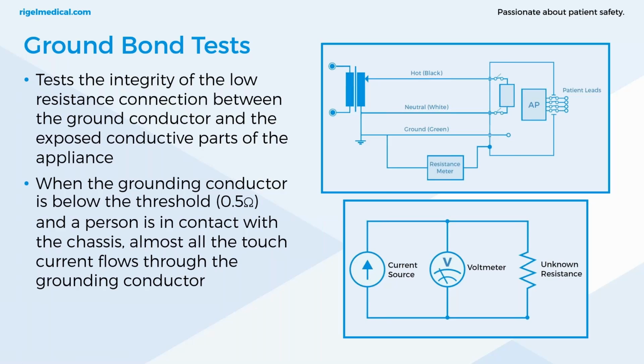Think of it like this: if the human body's resistance is 1 to 2 kiloohms, or the lowest value 1 kiloohm, even at the maximum allowable value of 500 milliohms, that's still 2,000 times less than the leakage current that would flow through the human body without that ground bond. Even at the maximum 500 milliohms, you're still going to have 2,000 times less leakage current flowing through the body than it would through that ground bond. And that's why we're measuring that value.